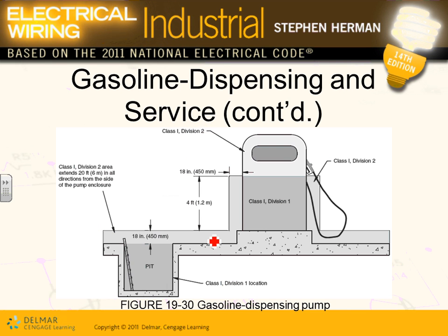So that's your equipment. Gas station. You guys go to gas stations all the time. If you have a pit in a gas station, typically you don't, but if you have a pit, your pit is a class 1 div 1, the worst of the worst, because the gas will accumulate there, and if it ignites, you've got yourself a bomb. If you don't have a pit, then it's 18 inches and up to 20 feet away from the pump, in every direction from the pump. This is class 1 div 2.